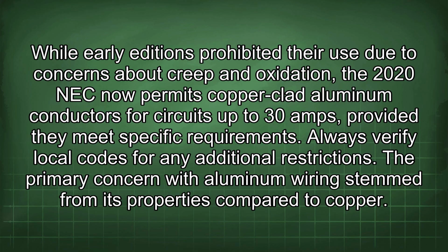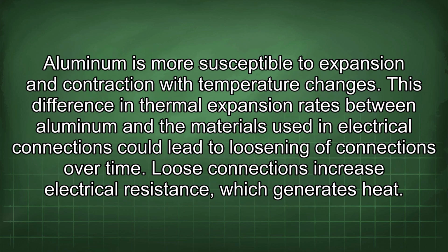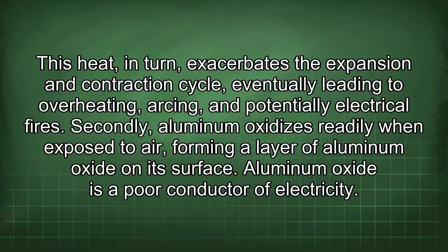The primary concern with aluminum wiring stemmed from its properties compared to copper. Aluminum is more susceptible to expansion and contraction with temperature changes. This difference in thermal expansion rates between aluminum and the materials used in electrical connections could lead to loosening of connections over time. Loose connections increase electrical resistance, which generates heat. This heat, in turn, exacerbates the expansion and contraction cycle, eventually leading to overheating, arcing, and potentially electrical fires.